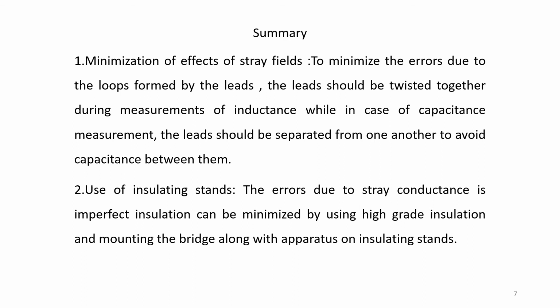To minimize the effects of the stray fields, to minimize the errors due to the loops formed by the leads, the leads should be twisted together during measurements of inductance, while in case of capacitance measurement, the leads should be separated from one another to avoid capacitance between them. Next, use of insulating stands. The errors due to stray conductance from imperfect insulation can be minimized by using high grade insulation and mounting the bridge along with apparatus on insulating stands.